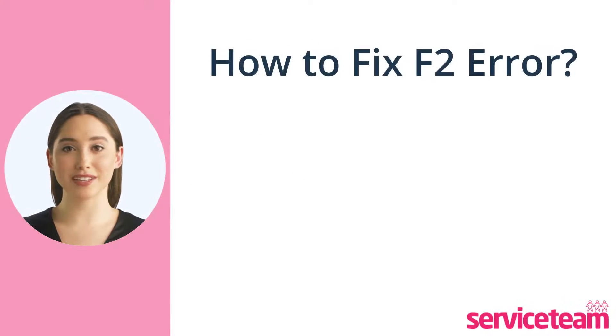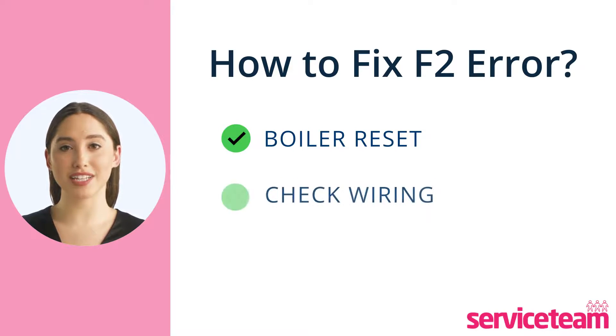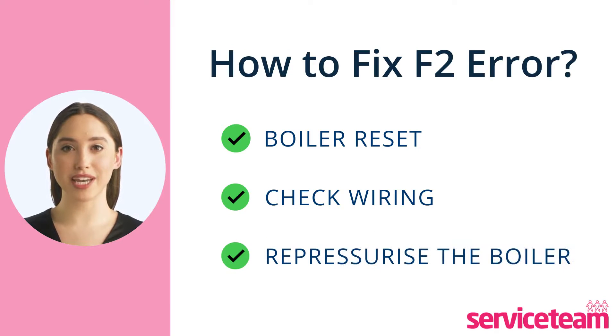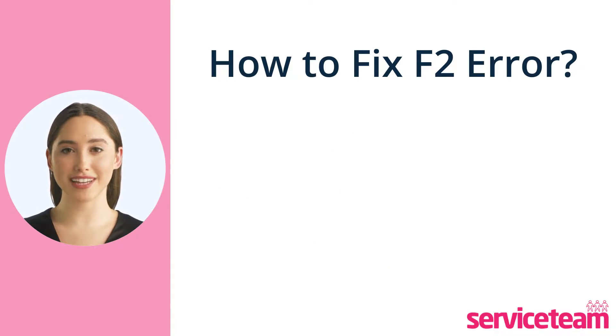Let's find out how to fix the F2 error code. Start by pressing the reset button under the boiler cover and wait for it to restart. If resetting doesn't work, check the wiring using a multimeter — make sure you know what you're doing with electricity. Low pressure might cause the error, so you need to repressurize the boiler; check your boiler manual to add more pressure if needed. Another way to fix the F2 fault is to thaw pipes, as freezing of the condensate pipe during cold weather can cause the system to fail.